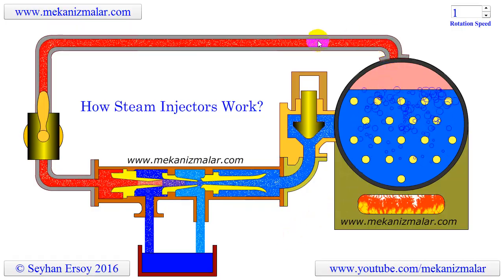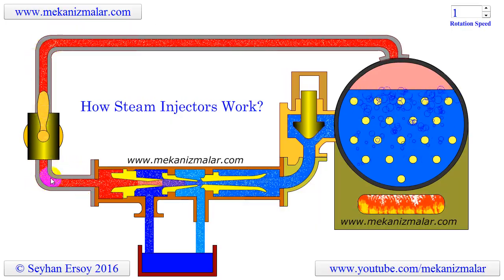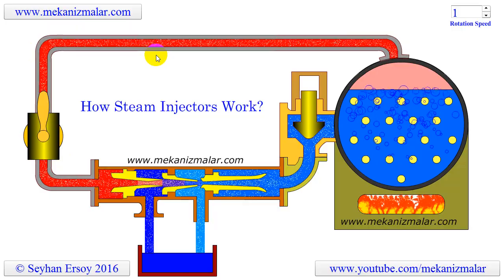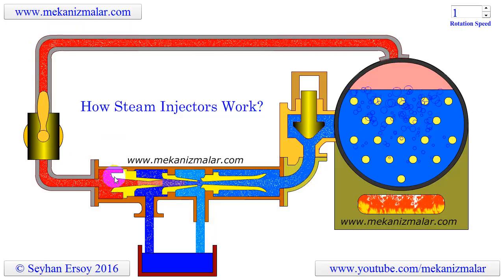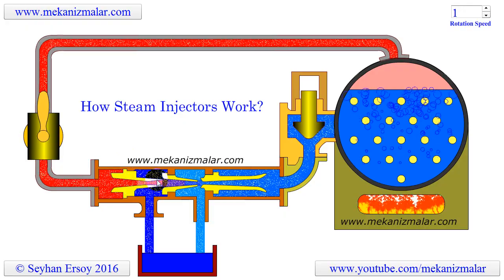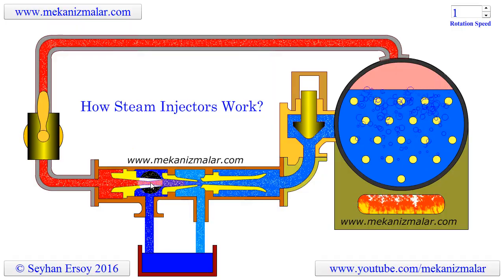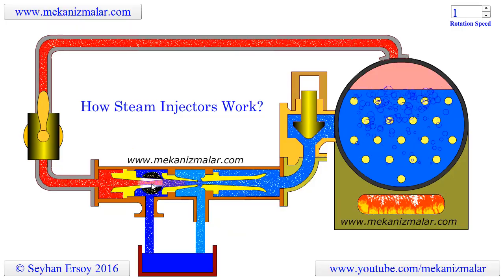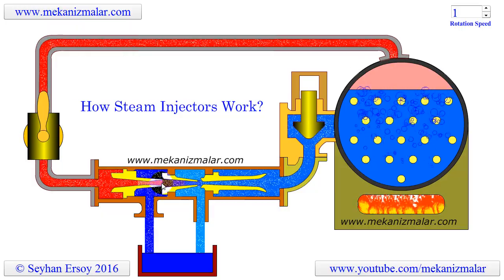Steam is taken from the boiler and delivered to the injector with high pressure and low velocity. This flow is directed to the converging-diverging steam cone. Where the cone is converging, the steam velocity is increased to the speed of sound. At the diverging section, the pressure is further reduced and converted to kinetic energy, where steam is moving faster than the speed of sound. By the time the steam leaves the steam cone, its speed is much faster than the speed of sound but the pressure is below atmospheric pressure.